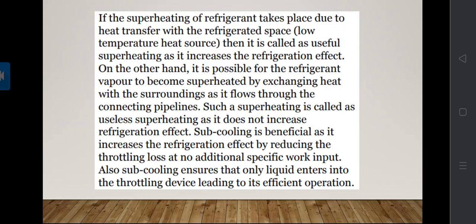On the other hand, it is possible for the refrigerant vapor to become superheated by exchanging heat with the surroundings as it flows through the connecting pipelines. Such superheating is called useless superheating, as it does not increase the refrigeration effect.